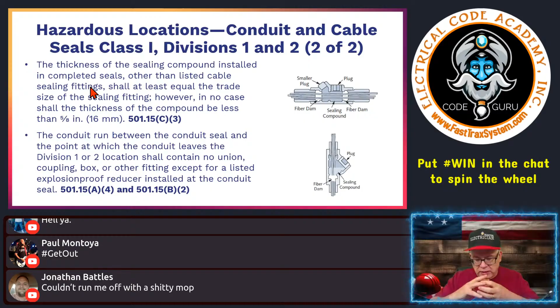I think Polywater makes specific sealed fittings now, or they bought a company that does. Those things are expensive - they're great, but they're expensive, and they're designed a certain way. You're not going to add compound to it. But you buy these seals with a plug, then you install it. Very common - I'm sure you've seen them where fuel filling stations have this set of nothing but different types of these seals. You have the fitting, and it aims up, and you basically fill it with your Chico or sealing compound, then you put it back and seal it. That type of thing.